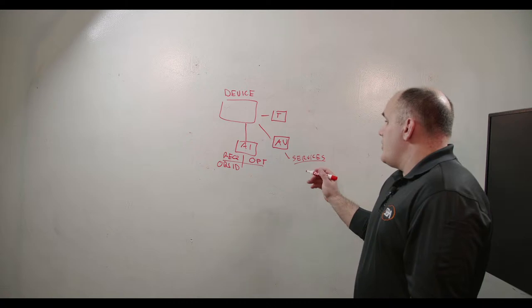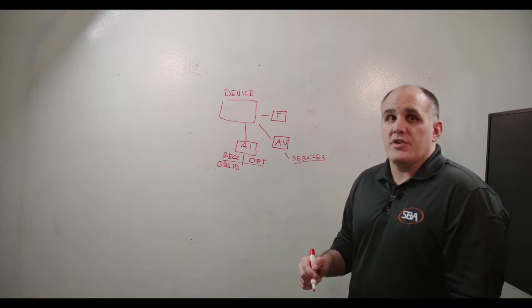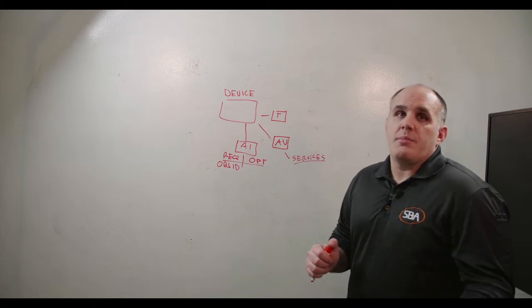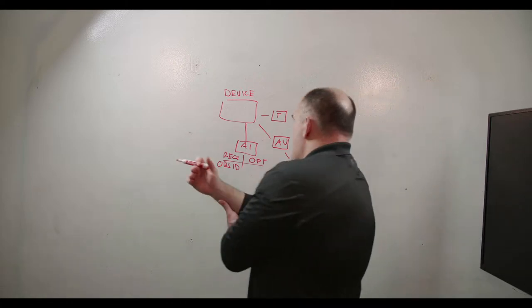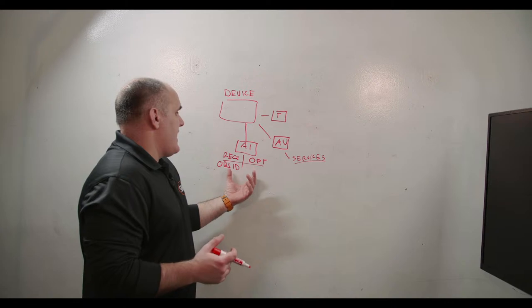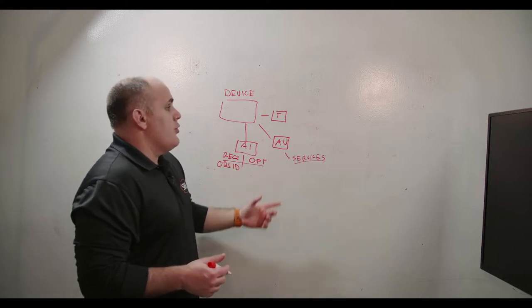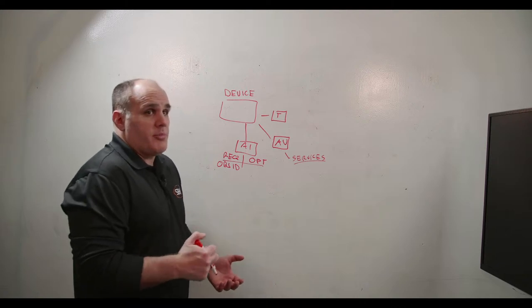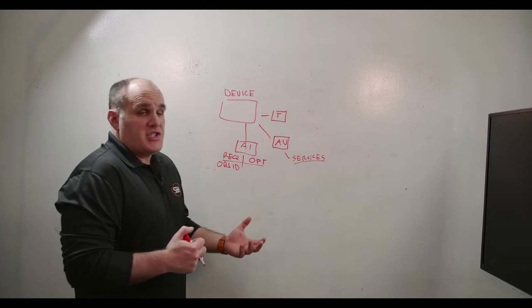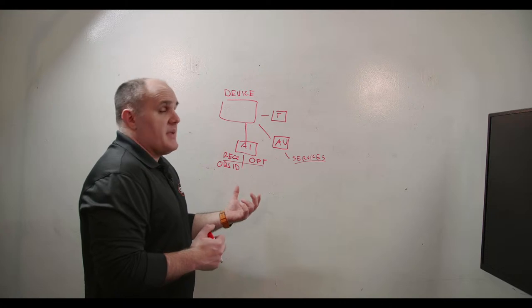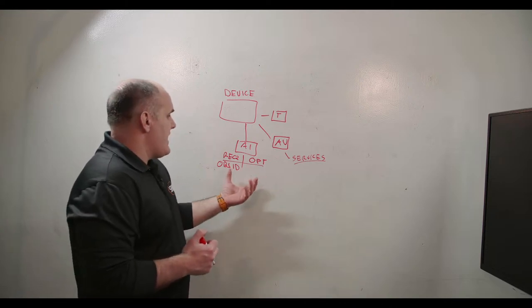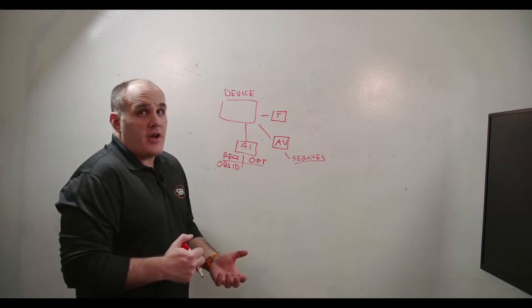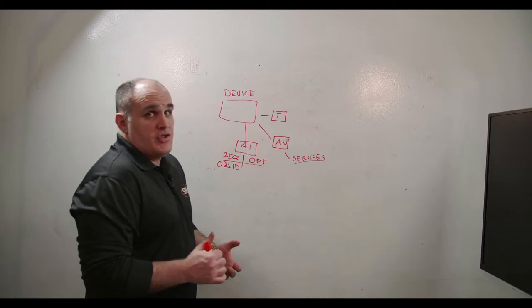The who-is/I-am is a broadcast service where a supervisory BACnet device discovers all BACnet devices on the network. There's also the time sync service. Understanding the services that objects and devices support is critical, because if an object or device does not support write property — for example, an AI does not support write property, it does not have a priority array, and thus has nothing to be written to — whereas AVs and AOs do support the write property service.